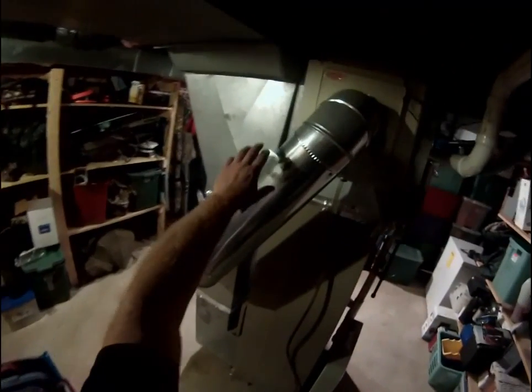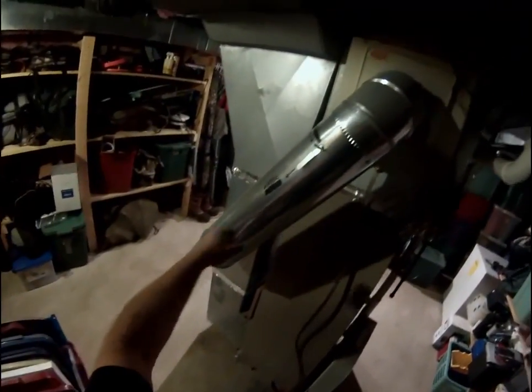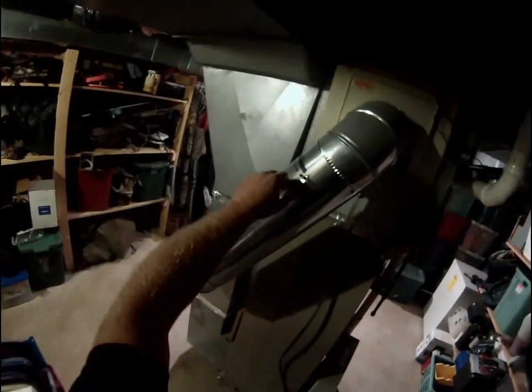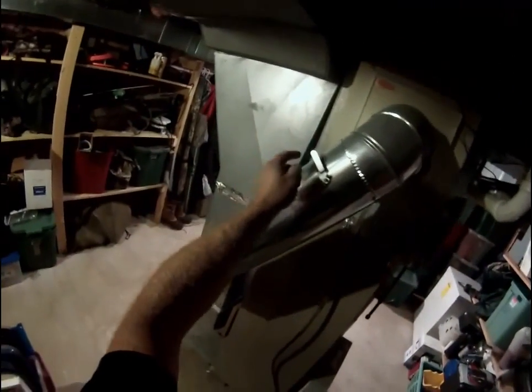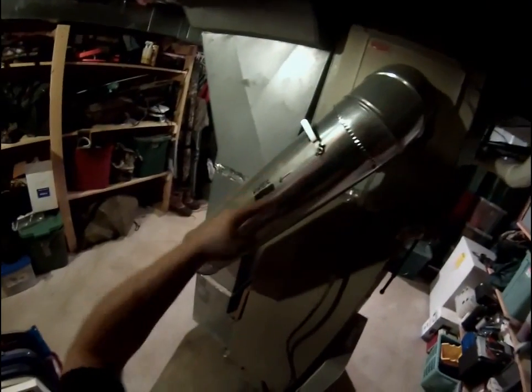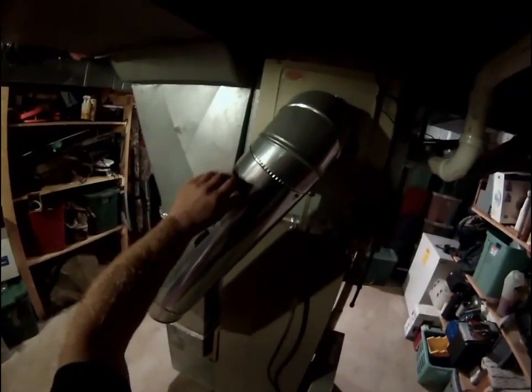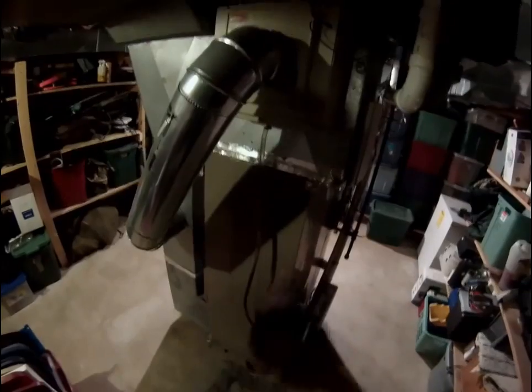Another access sometimes you can get at your air conditioning coil is on humidifiers. First off, if you're freezing up, another thing you want to check, if you have a bypass type humidifier that blows air from the supply to the return, make sure that that's closed. It's going to be closed in the summer when you're running your cooling so it doesn't blow cold air right around in a circle. Because real cold air inside there will also cause it to freeze up.